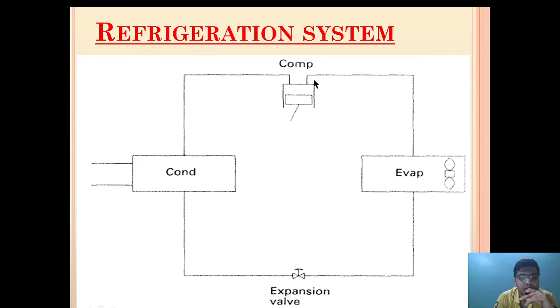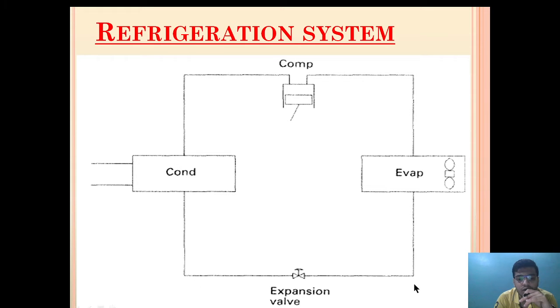As the compressor increases the pressure, the refrigerant is in vapor form at high pressure. After it has been cooled by the condenser, it is converted into liquid form, but still at high pressure. As it passes through the expansion valve — which converts the high pressure to low pressure zone — it is still in liquid form. From the expansion valve to the entry of the evaporator, low pressure liquid refrigerant enters the evaporator, extracting heat from the environment and converting into gas form, which then goes back to the compressor.